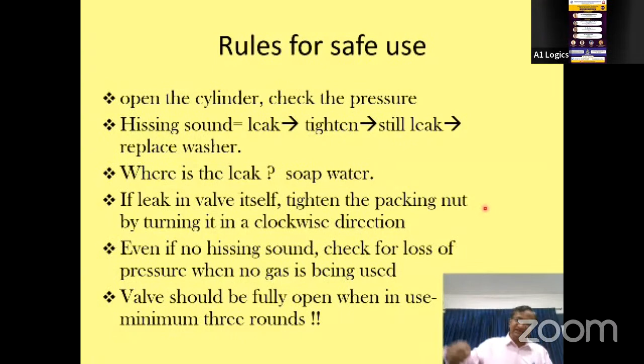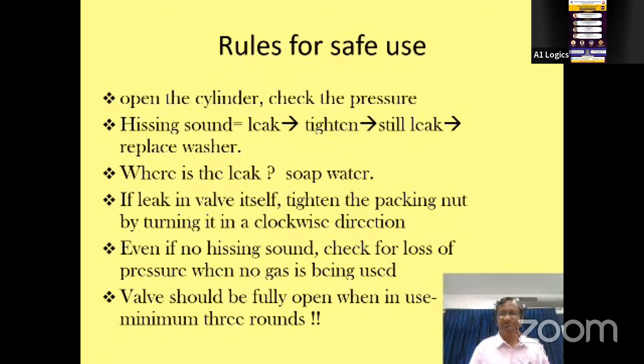Cylinder tightening is different from packing nut tightening. If there's no hissing sound, check for loss of pressure, and the valve should be open. Many people open the cylinder and stop, but that's wrong. You should do a full 3 rounds to say you have opened the cylinder valve. If you only go 1.5 rounds, good pressure may still come, but that's not right. Whenever you say you have opened the cylinder valve, it means you should completely circle it 3 times.